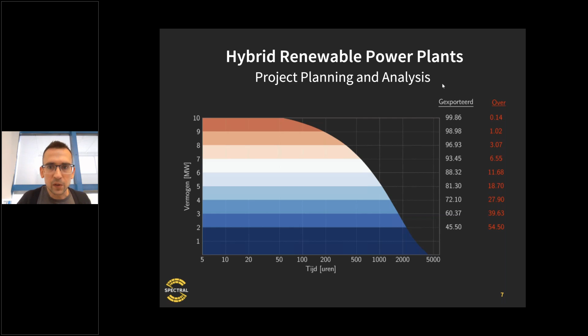In this case, we'll be putting about an 8.4 megawatt-hour installation behind this solar plant, behind the same 10 MVA connection. Adding that extra 8.4 megawatts of battery capacity will only increase curtailment by about 0.2%. So in total, we can have 13 megawatts of solar plus 8.4 megawatts of batteries and waste only about 0.3% of the total solar output of that plant.